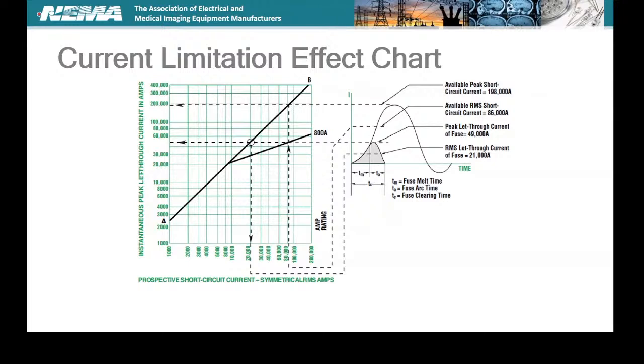So you've reduced the heat, you've reduced the magnetic forces on the power distribution system by operating that fuse in its current limiting region. Now, remember, fuses love current. If that fuse doesn't see enough current to be in its current limiting region, now you're in the long time region. That's when you can run into incident energy issues and things of that nature, because now you're into seconds. Once that curve crosses 0.01 seconds, any currents greater than that point, you're into the current limiting region of that fuse. Hopefully that helps. Right. That's great.